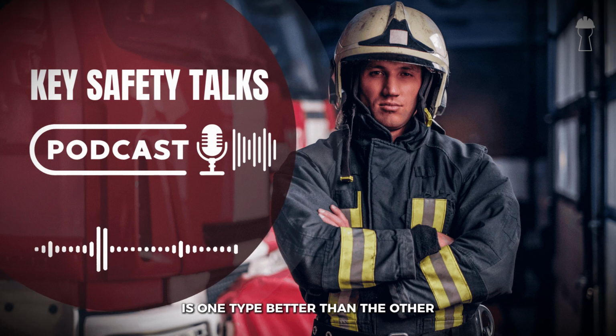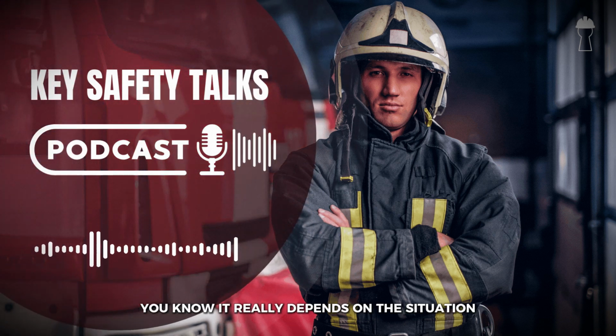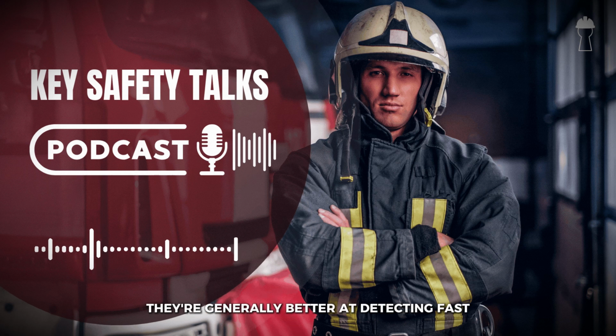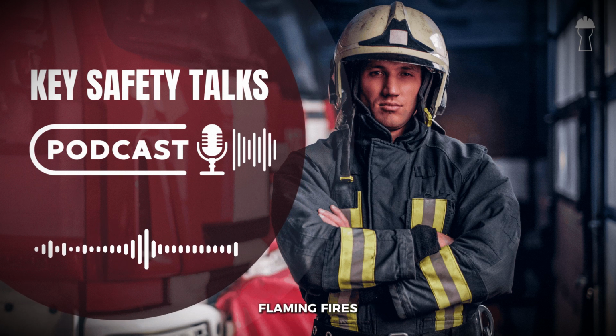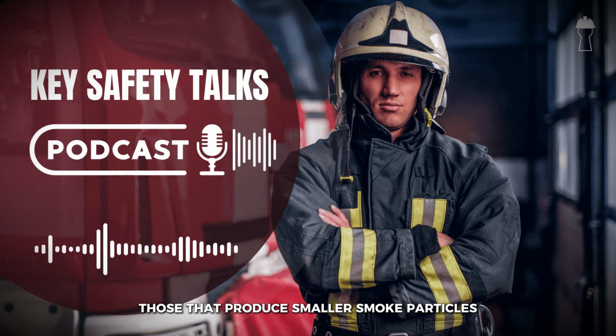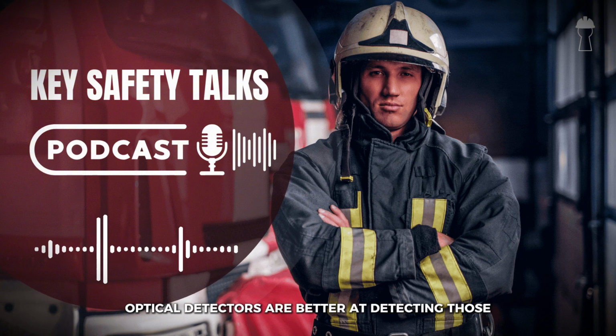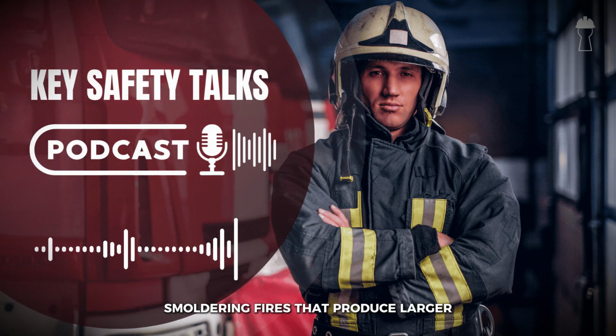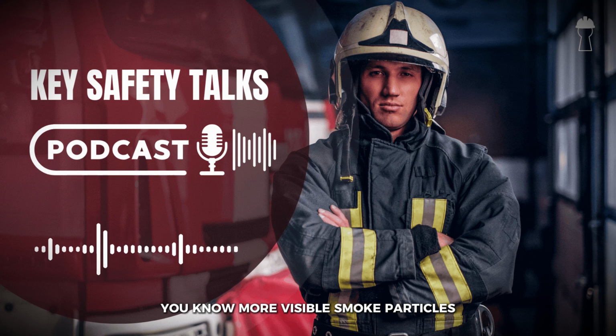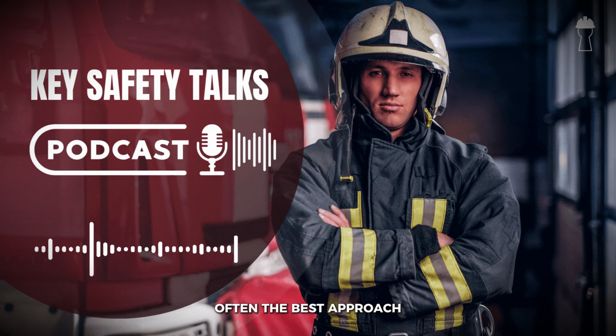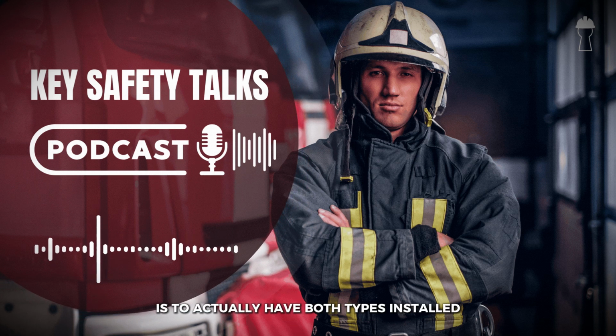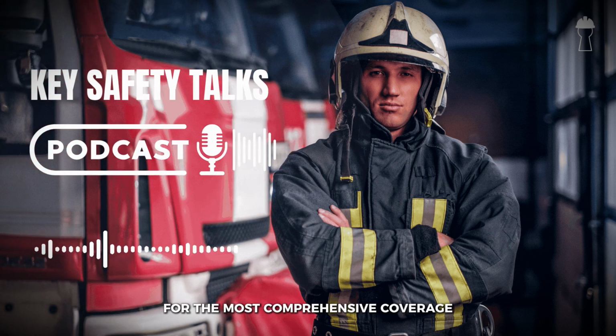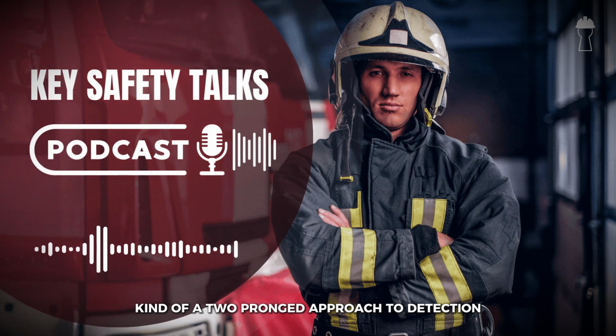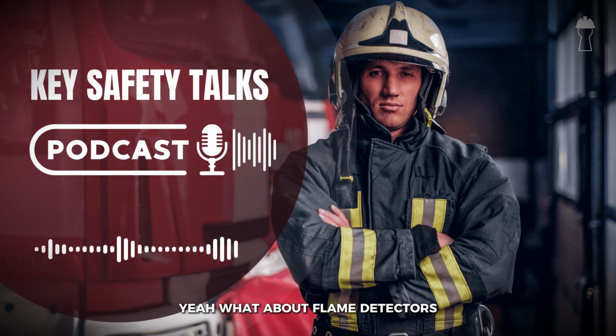Is one type better than the other? It really depends on the situation. Ionization detectors are generally better at detecting fast-flaming fires, those that produce smaller smoke particles, while optical detectors are better at detecting those smoldering fires that produce larger, more visible smoke particles. So often, the best approach is to actually have both types installed for the most comprehensive coverage. That makes sense. Kind of a two-pronged approach to detection. Yeah. What about flame detectors?